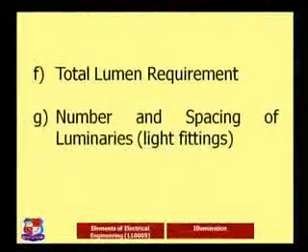The last one is the number and spacing of luminaires, meaning light fittings. At how much distance we have to put the fittings and how many we require is again going to be important. It should not happen that for a particular small area there are 100 fittings, which is useless and creates glare. At the same time, for a large area we should not have very few illumination sources. So as part of the design, along with the total lumen required, we also have to calculate approximately at the designing stage how many fittings we require.